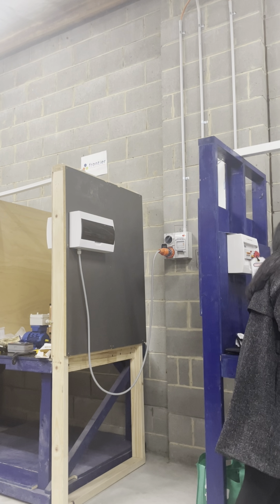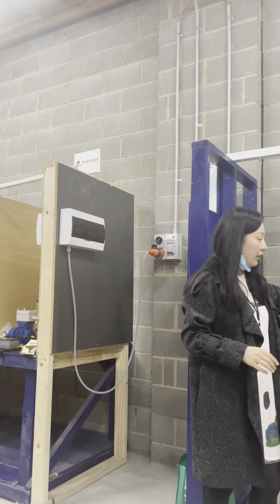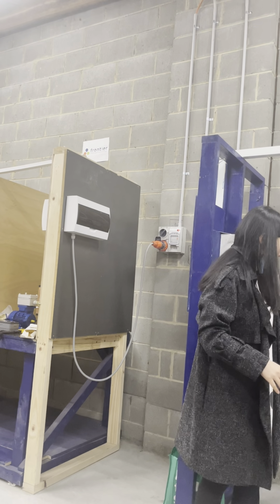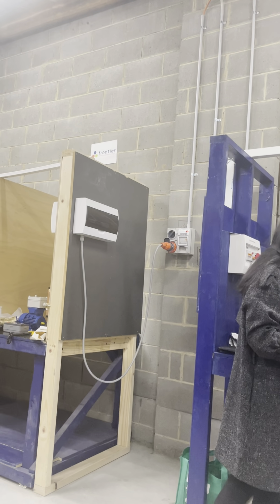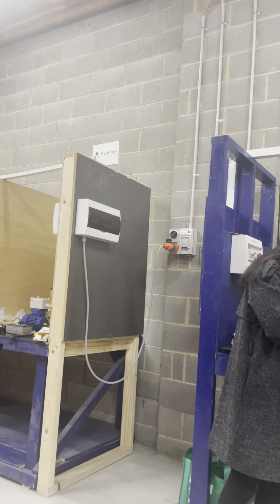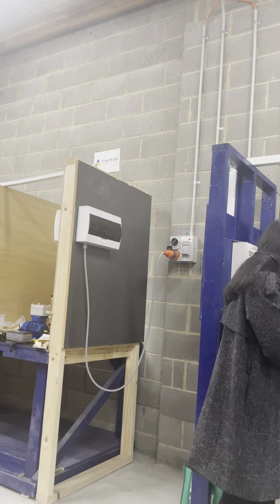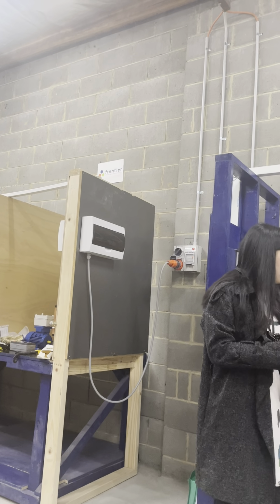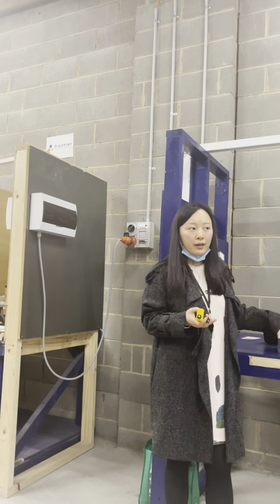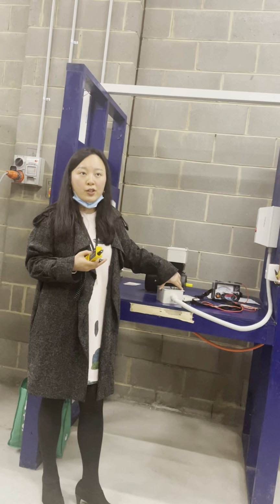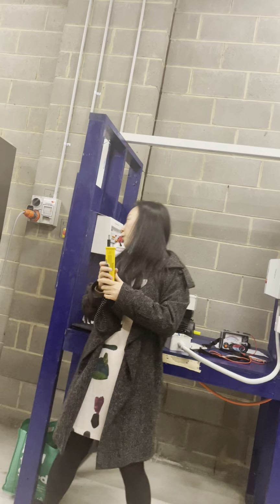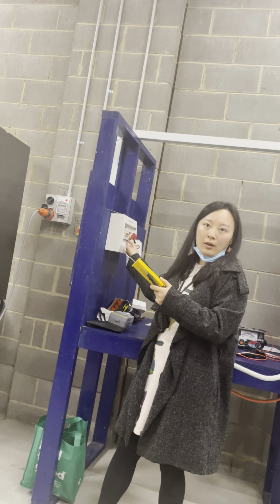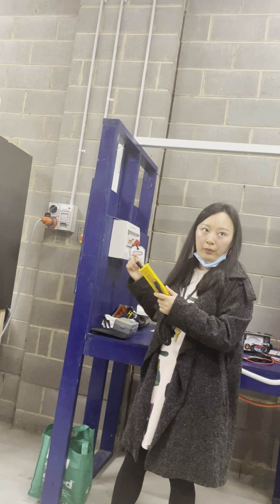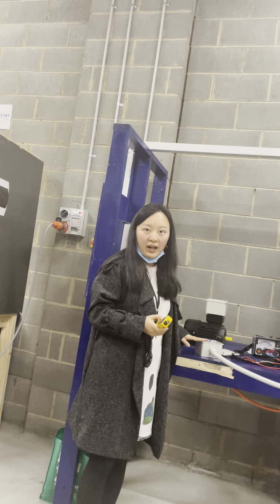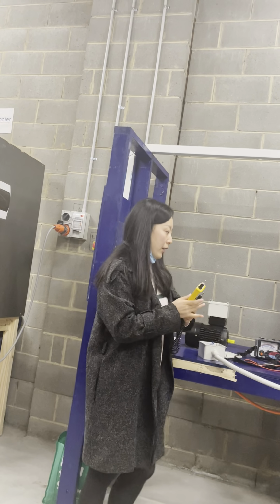Let me close the cover. But if you don't, that's fine, because you are still in the same room. But when you go to the switchboard, you must leave this closed. Now we need to work on this termination of cables. The reason for this test is that you wouldn't know if someone's changed the circuit breaker, even though you physically see it's still the same one, but maybe it's not the same circuit breaker anymore. So we need to make sure there is no line voltage on the terminal. So test your tester.